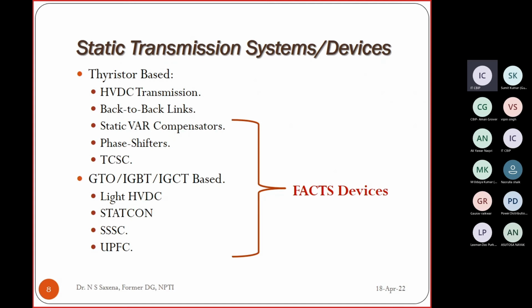These devices, in fact, simplified the whole thing. The conventional HVDC was very huge. Then with voltage source converters, VSCs, they started calling it HVDC light because it became light - it doesn't require huge reactive power support. HVDC light, basically VSC based, requires filters, but filters are required only for harmonic suppression, not for reactive power support.